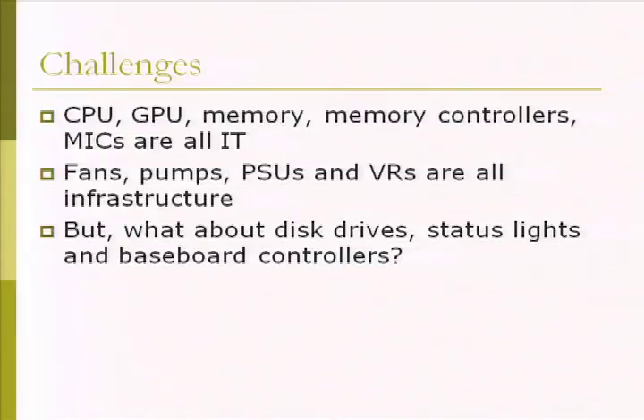Okay, beyond the 1.0: when we first defined PUE, the average was around 2. It still is around 2 for most data centers because of legacy issues — people can't or don't want to totally redesign their data center. You can get it to about 1.5 by redefining things; best practices in airflow management and similar measures can give you a PUE of about 1.5. If anybody wants information on how to improve the energy efficiency of their data center, we have resources that can help.